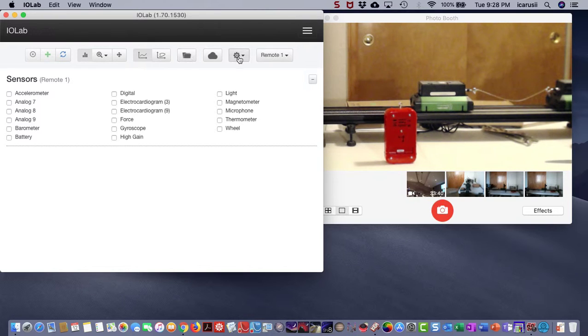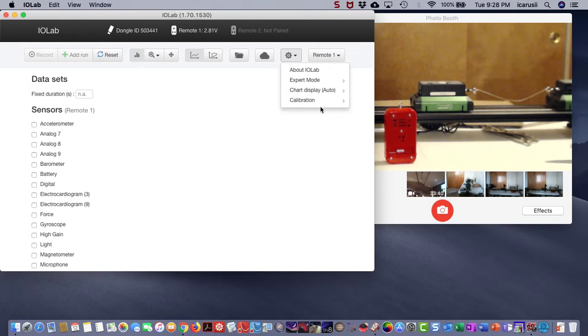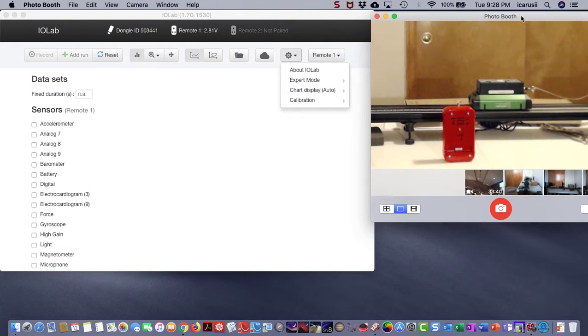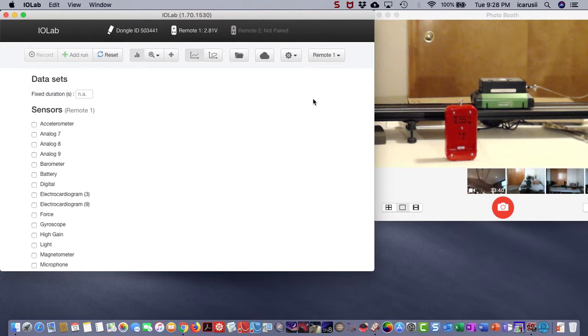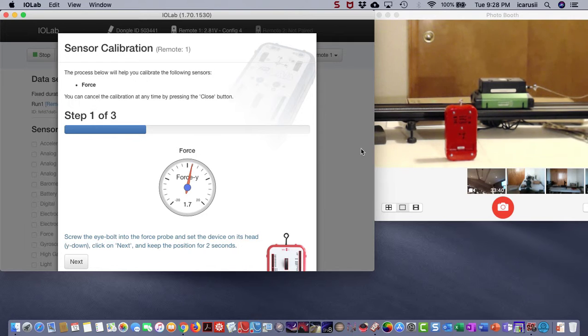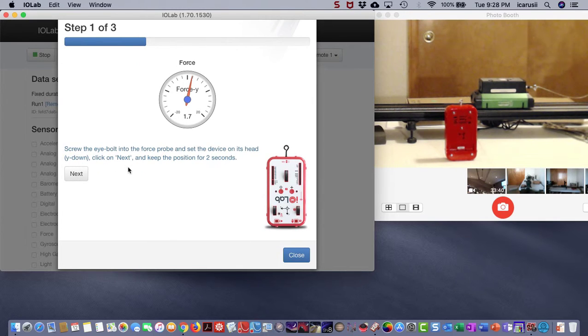So let me go ahead and get into calibration. You click on the control panel and click calibration, and my panel is a little wide, so let me just do that. So I'll click on this calibration, and I want the force sensor. Once you get there, you see that the force sensor is on, and this is not shown in the picture, but the USB drive is flashing. The IO Lab device is taking some data, and you can see that there's a force Y of 1.7, 1.8 thereabouts.